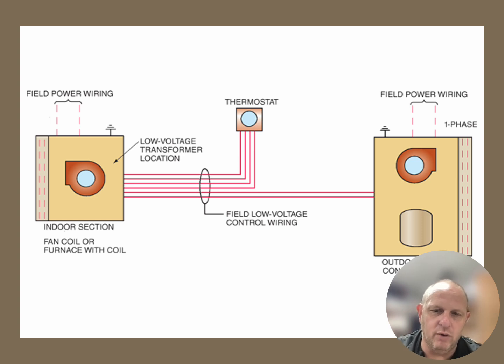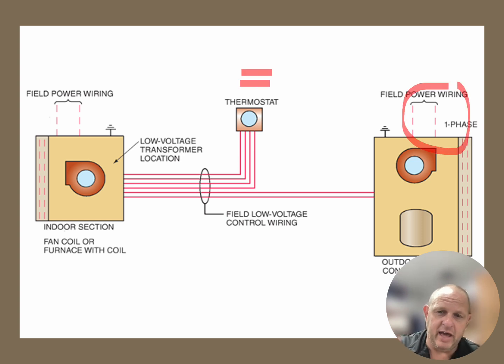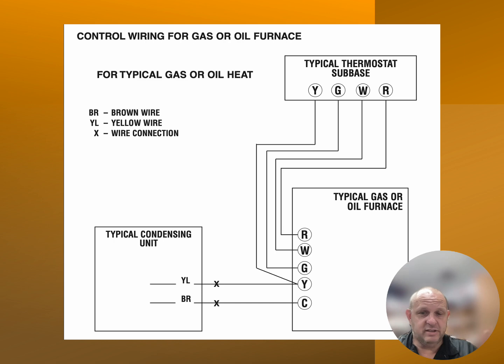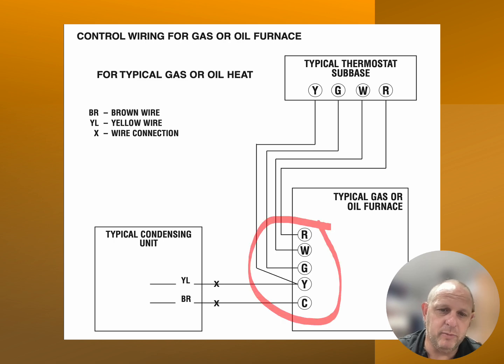Every time you see a dashed line, like we are seeing here, that means that is field installed wiring. Whether that's low voltage or high voltage, dashed lines are wiring that the technician in the field is going to be accomplishing for that particular unit. Typical wiring for a single stage air conditioning unit with a gas heater or an oil heater that's hooked up to it. All the connections are going to be made on the indoor unit. R is for power, W is for heat, G is for fan.